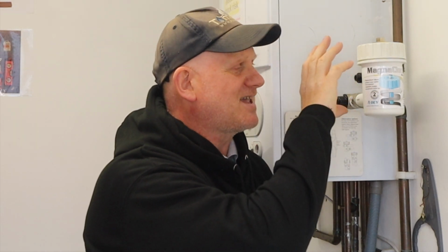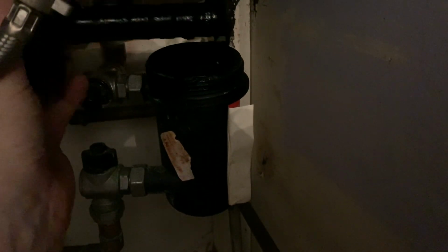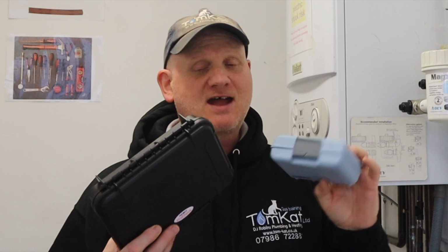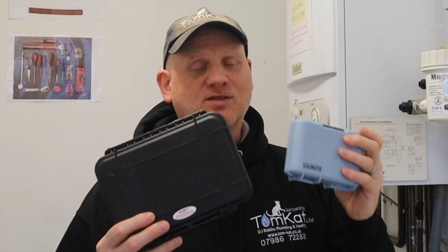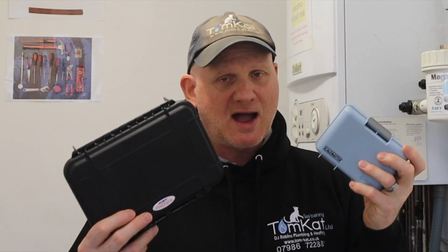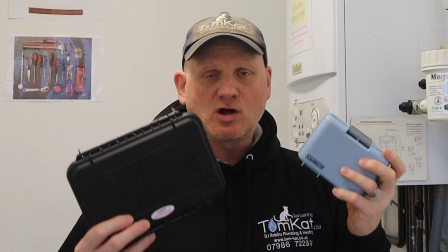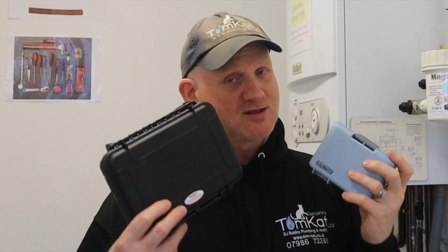Magnetic filters are key to keeping your boiler going longer. Now, these magnetic filters are the last line of defense to protect your boiler from magnetite, sludge and corrosion. It's your water quality inside your system that you need to be worried about, and there are loads of different tests out there on the market that you can buy to actually test the water quality of your central heating system, because that is key.